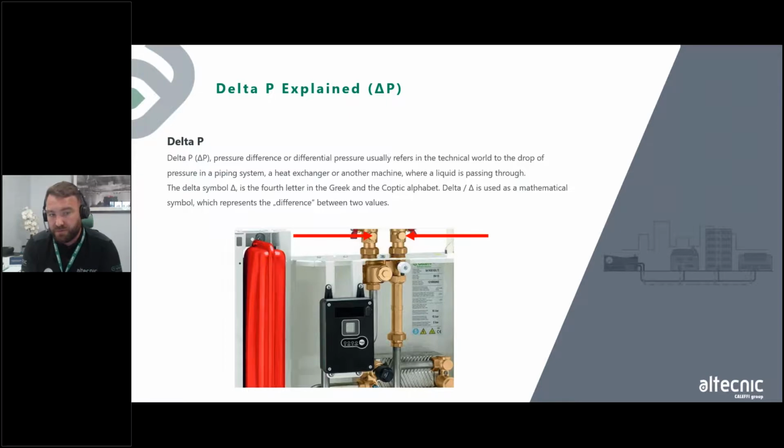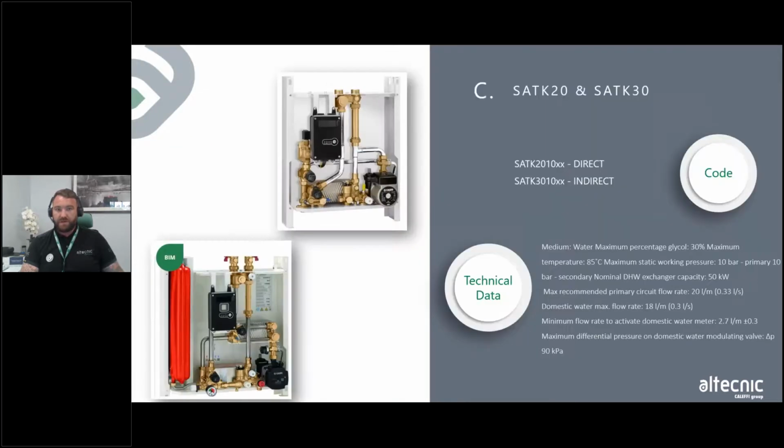So we know whether the HIU is operating within its energy levels as well. Not a lot of people carry manometers. There is a way you can work it off the heat meter via the temperature and the flow, but predominantly we use a high pressure manometer within those binder ports to make sure that we're getting enough energy into the HIU itself, to make sure it's working as it should be. So very important. We need a high delta T, and we have to make sure that the delta P is well within the operating conditions of what the HIU requires.